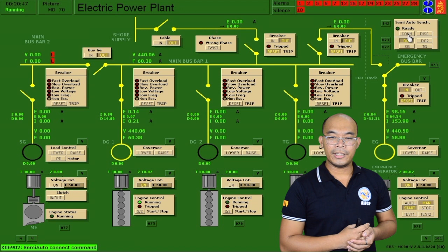Okay, now we can start the voltage controller for diesel generator 1. Hintayin lang natin na mag-steady yung voltahe niya around 440 volts. We can also adjust the voltage at saka yung frequency sa governor. Now we can use the semi-automatic synchronization panel, i-click mo lang yung DG1 and then connect. Okay, and then i-connect natin yung mga bus tie natin. This will supply the power towards our loads.